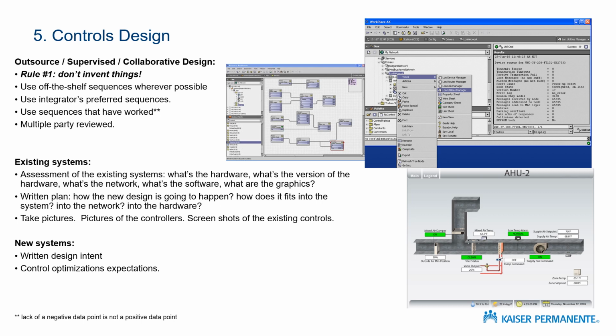Primarily, we don't know any design firms that have controls programmers in-house, and we know only a few design firms that have dedicated controls designers in-house that do controls design 40 hours a week. And so the ideal model is more of an integrated model where the engineer of record, the commissioning agent, the controls integrator, and all the major equipment manufacturers collaboratively author the controls design and the sequence of operations. So where we can make that happen, that's what we're doing.